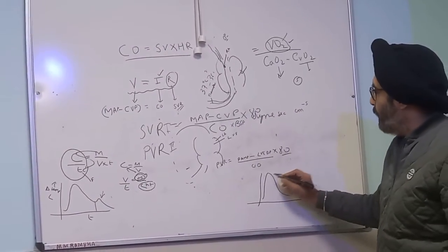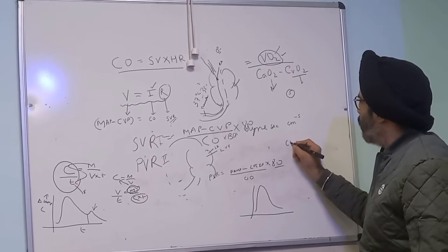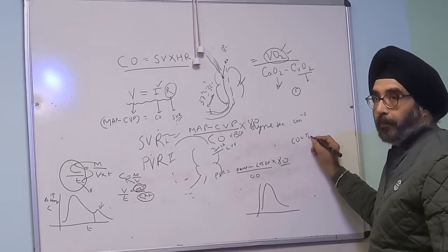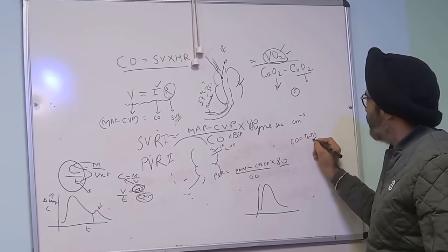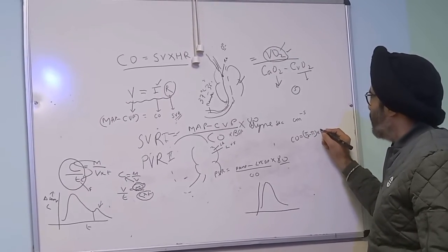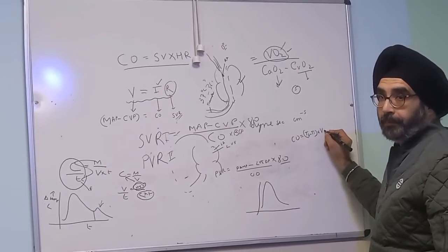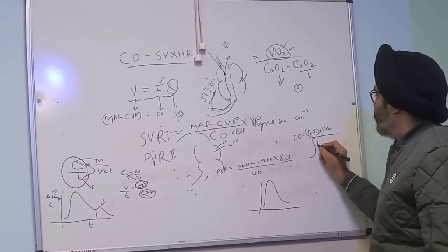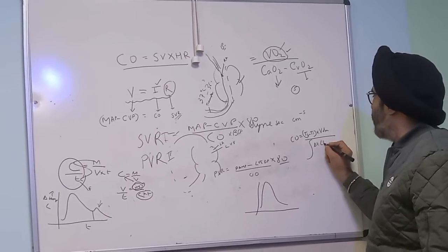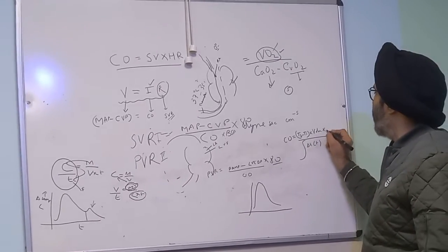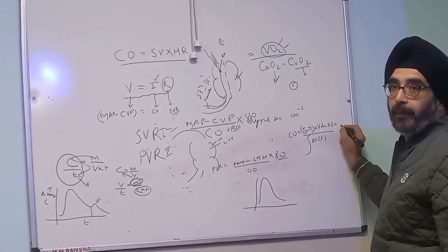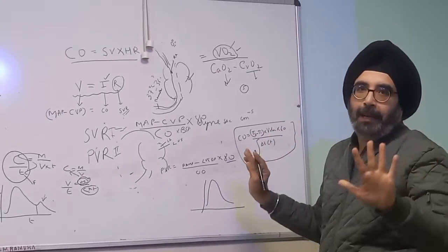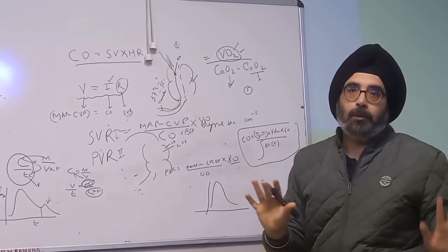So in this, we have the formula: cardiac output equals the temperature of the blood minus the temperature of the injectate, multiplied by the volume of the injectate, divided by the integral of the change in temperature with time, multiplied by a factor of 60 seconds. Okay, so we use this formula. We should have an idea basically of how to calculate the cardiac output.